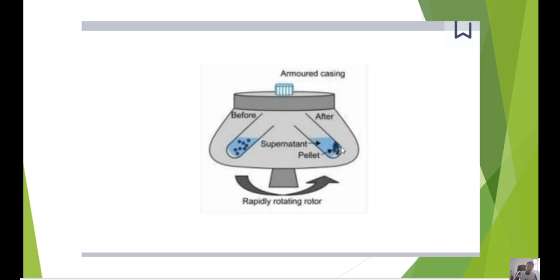Okay, so the rate of centrifugation is specified by the angular velocity, usually expressed as revolution per minute, or acceleration expressed as g. The conversion factor between the RPM, which is the revolution per minute, and gravity depends on the radius of the centrifuge rotor. So there's a relationship between that. Now, you just put it in a centrifuge and then it begins to rotate rapidly. As it's rotating, you notice that before they used to be suspended on top, but now, after centrifugation, they are pushed towards the bottom. And after this is happening, you can actually now separate the mixture.